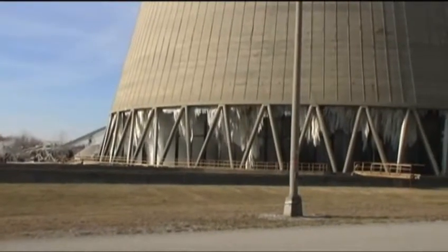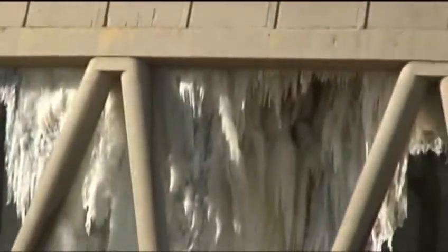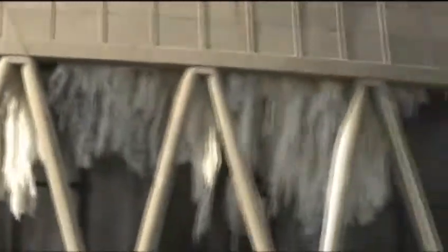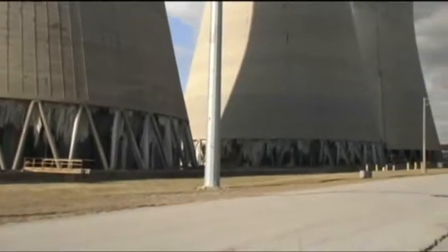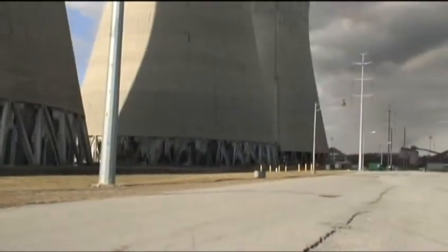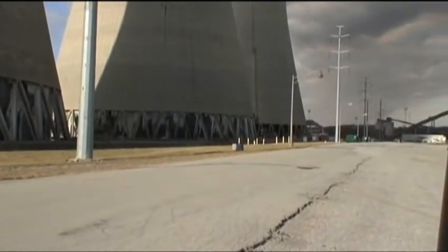There's where air monitoring is in the basin currently. There's air monitoring up on top as well. Here we are down by tower 3. See what happens when the cold weather is about 20 some degrees. It freezes the water, sticks to those inner cells, and then falls off. Give you some idea of what happens. This is the next one we're going to be doing, tower 2, and then we're working all the way down to tower number 1, way down there.